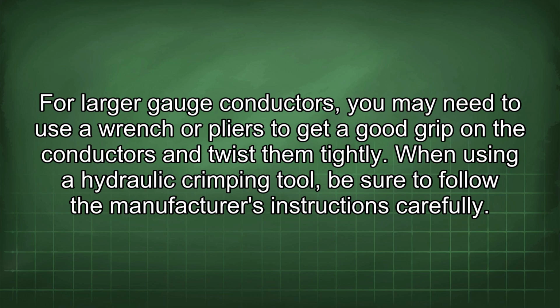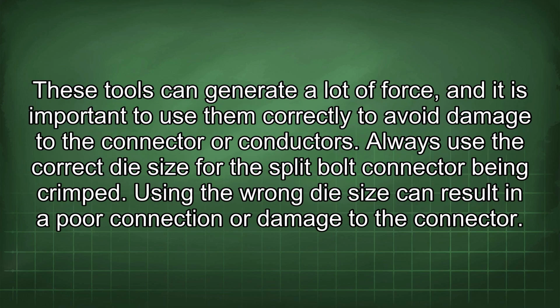When using a hydraulic crimping tool, be sure to follow the manufacturer's instructions carefully. These tools can generate a lot of force, and it is important to use them correctly to avoid damage to the connector or conductors. Always use the correct die size for the split bolt connector being crimped. Using the wrong die size can result in a poor connection or damage to the connector.